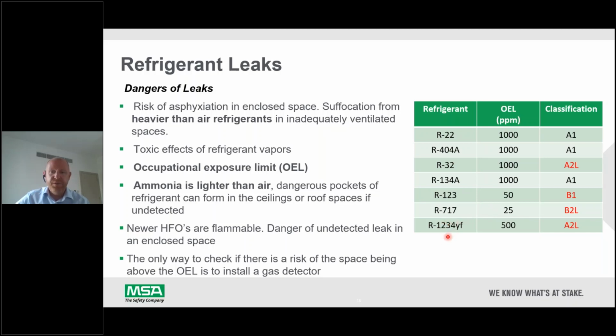And for the newer refrigerants, because of the flammability issues, you need to be able to detect them at low levels. The only way of detecting if this level of gas is in your plant room is to install some form of leak detector to check the ppm levels of that area. So in order for you not to get to the high level of 1,000, you would have different alarm levels, maybe at 50 or 250. So you can detect the leak at a very early stage and fix it before it gets to these levels.